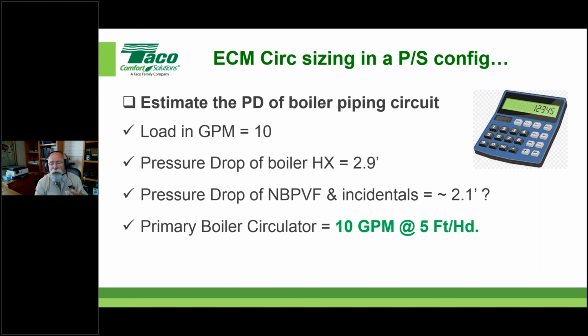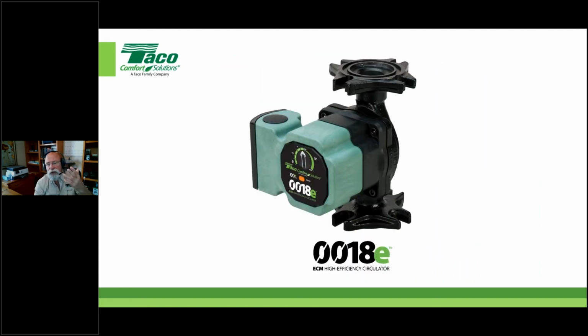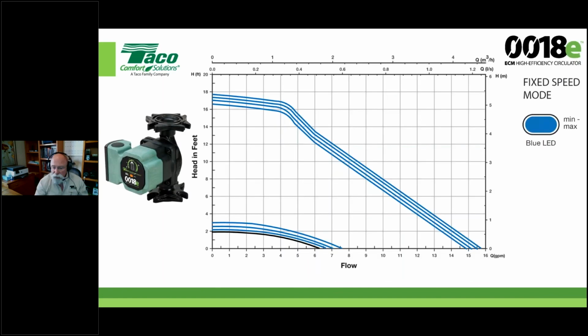Okay. So in this case, I've got a primary boiler circulator with a requirement of 10 gallons a minute at 5 feet of head. Voila. I have the ability to come up with a circulator and make sure it's the right one for the job. Of course, I'm putting my best foot forward here with our 0018E for one specific reason. Again, just like I said, this doesn't have 0 to 10 or pulse width modulation yet. But what I can do with this, as I mentioned early on, is appropriately set the GPM of this pump to what's correct for that specific application you happen to be working on. Remember, with the fixed speed mode of this pump, we can turn it up or down anywhere between 4 watts and 44 watts.